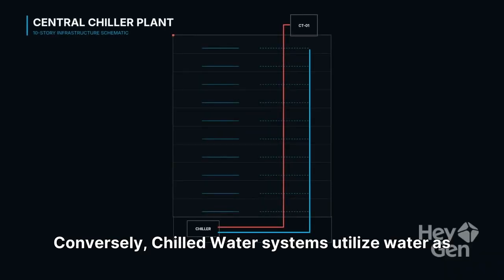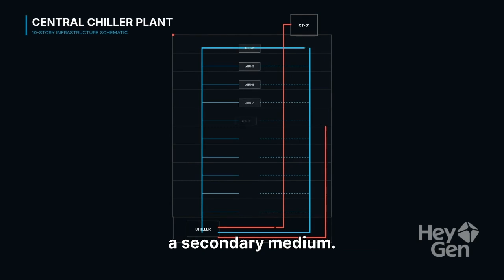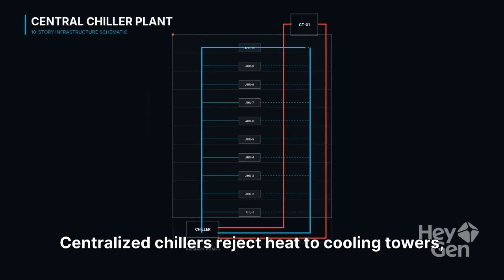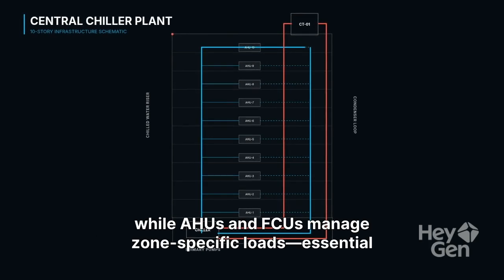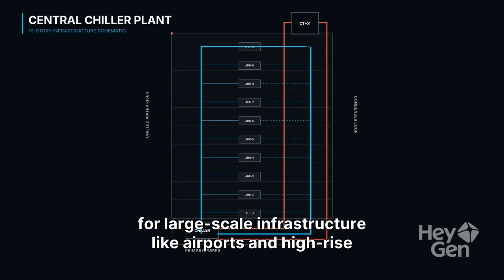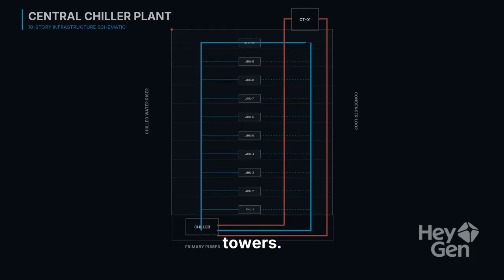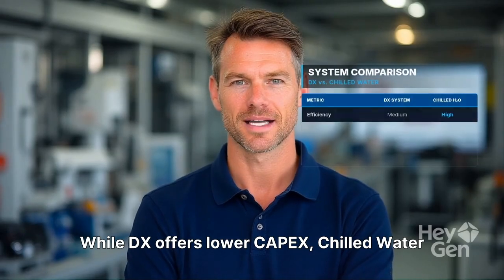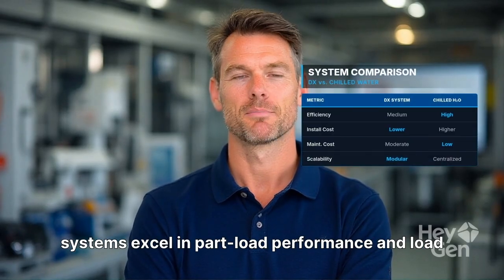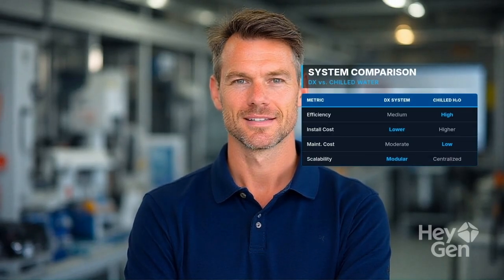Conversely, chilled water systems utilize water as a secondary medium. Centralized chillers reject heat to cooling towers, while AHUs and FCUs manage zone-specific loads, essential for large-scale infrastructure like airports and high-rise towers. While DX offers lower capex, chilled water systems excel in part load performance and load diversity.